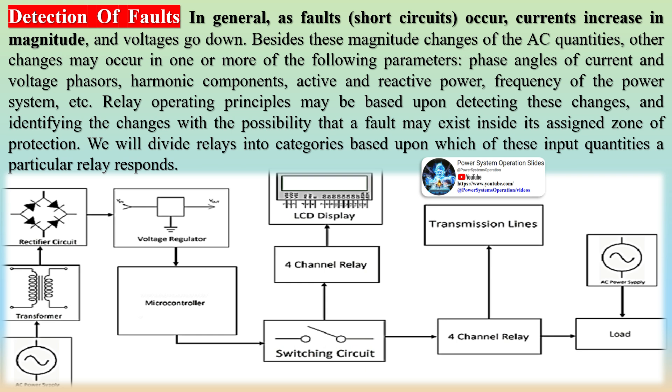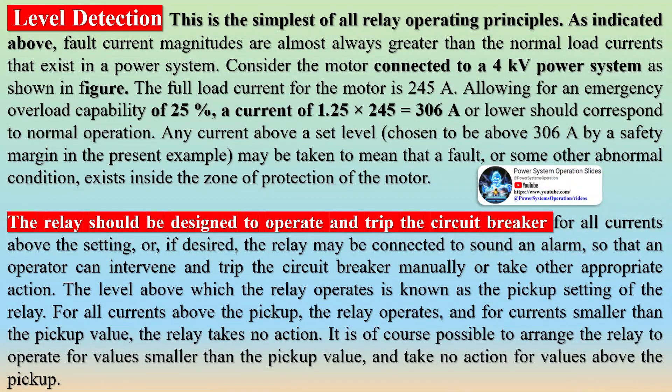For example, consider the relay shown in figure. If one were to use the magnitude of a fault current to determine whether some action should be taken, it is clear that a fault on the inside fault F1 or on the outside fault F2 of the zone of protection is electrically the same fault, and it would be impossible to tell the two faults apart based upon the current magnitude alone.